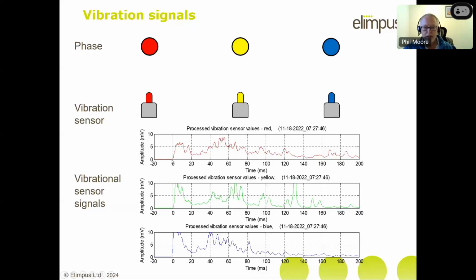open operation. You can see this large buildup of vibration energy, which occurs more or less on this particular circuit breaker, which didn't have a controlled switching relay. It actually occurs exactly at the same time on all three phases. But I'll have a few more words to say about vibration in a moment, but there are some very obvious defects that can be detected by looking at the vibration.